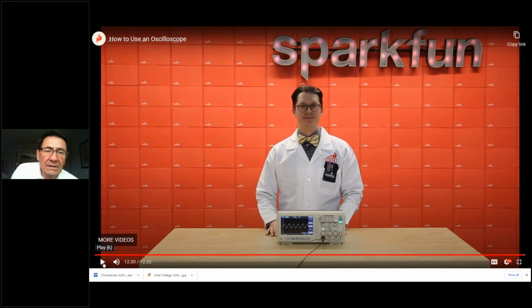The last thing he mentioned before that joke was he pulled that thing out of his pocket. It's a USB scope. I want to point out that the Drive Wizard makes your laptop into a scope, albeit with a very low bandwidth. Yet the Drive Wizard, with its low bandwidth and low sampling rate, is just fine for reading most of the data we're trying to trend on a VFD.